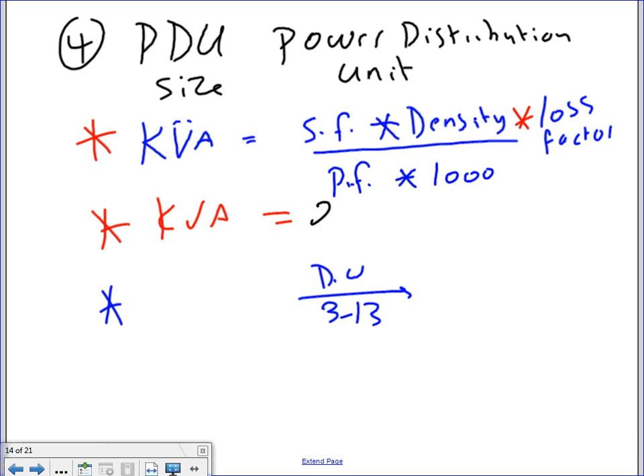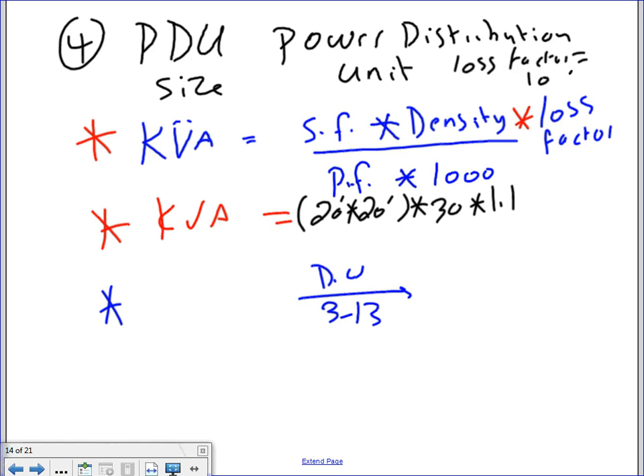So I'm going to use 20 times 20. You guys remember that 20. Multiply this one by, the density was 30. Multiply this one by 1.1. The loss factor of the PDUs, we're going to assume the same loss factor, guys. There's a loss factor, there's transformers, right? You're going to have losses in them. We'll assume 10% loss factor. Can I add this one? Loss factor equal 10% loss factor.